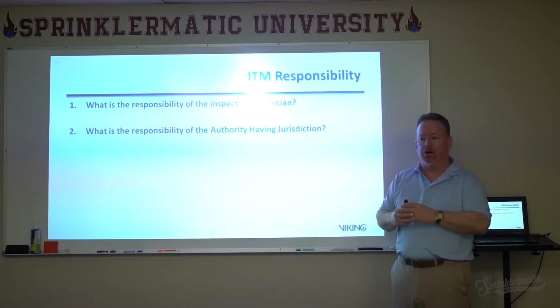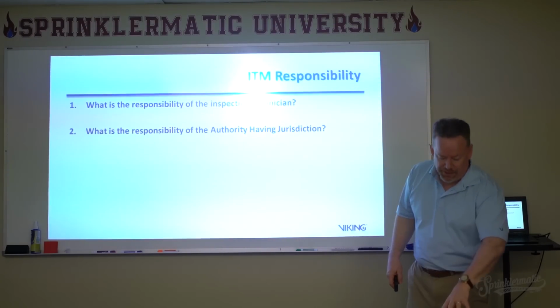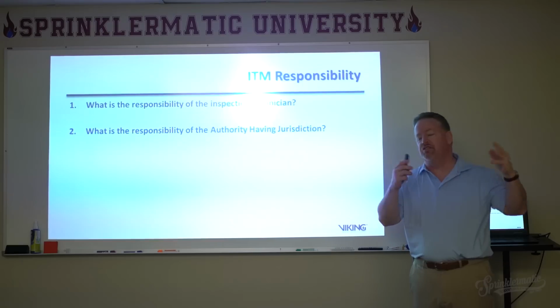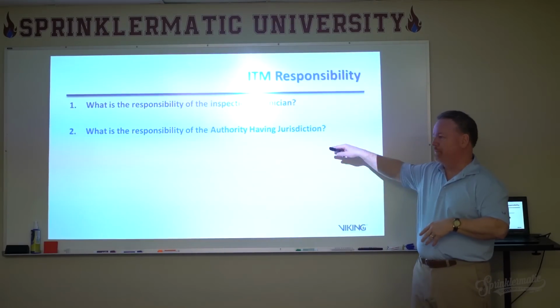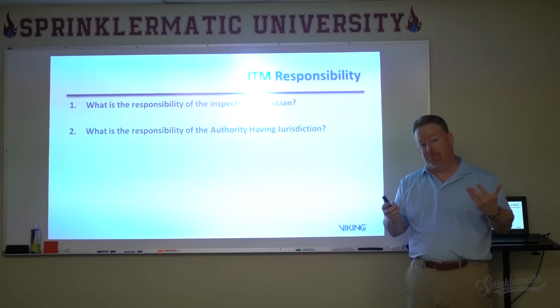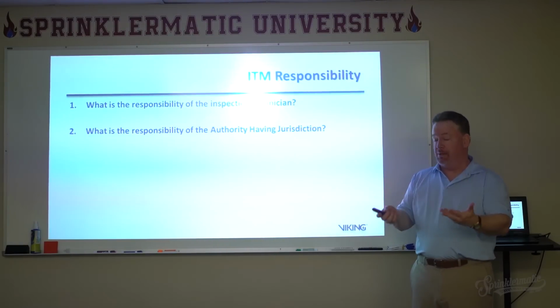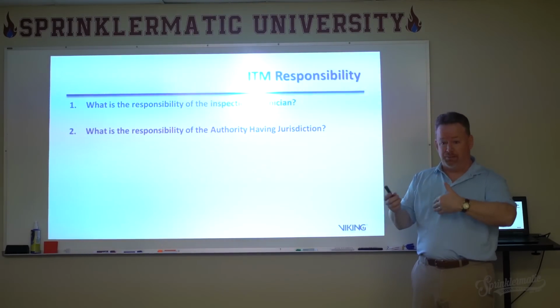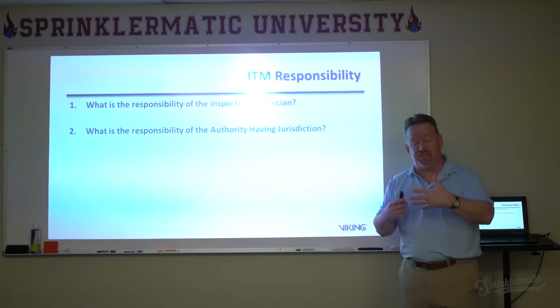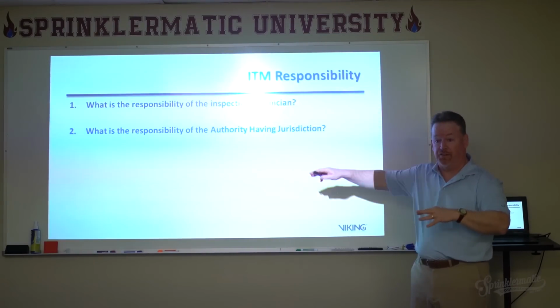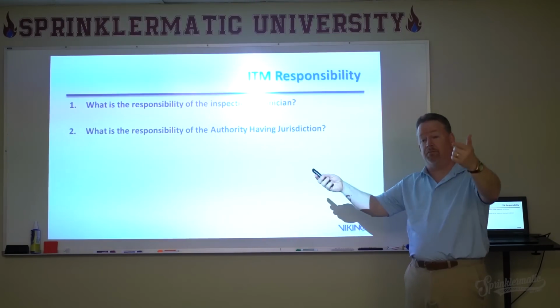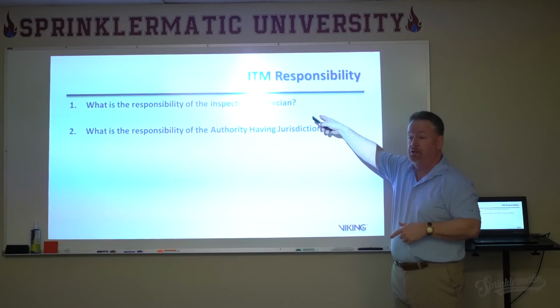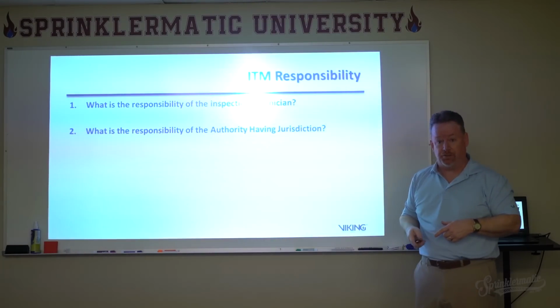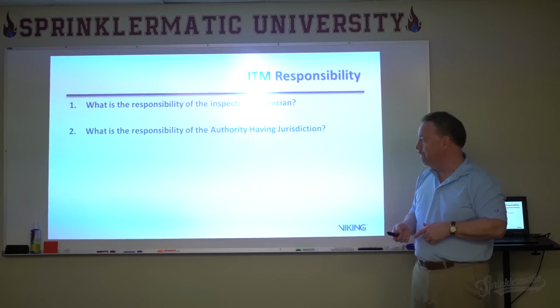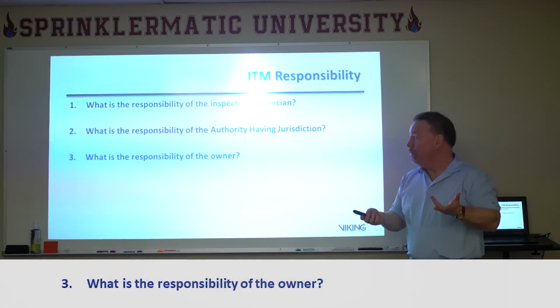NFPA 25 has a number of things the inspection technician does that the authority having jurisdiction, by virtue of getting the reports, can become aware of. But we need to be careful not to mistake that as a requirement of NFPA 25 for the inspection technician to give that material to the authority having jurisdiction. We'll get to that in a moment, because the last question is: what's the responsibility of the owner?